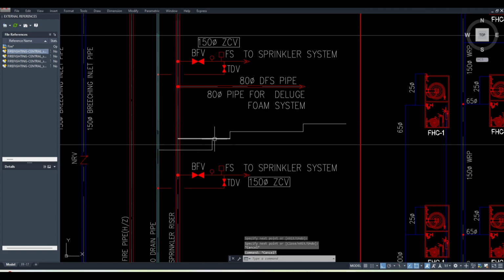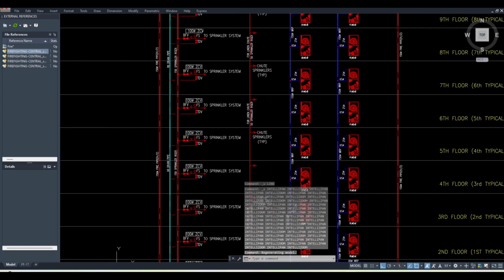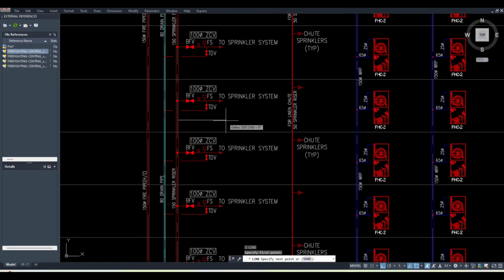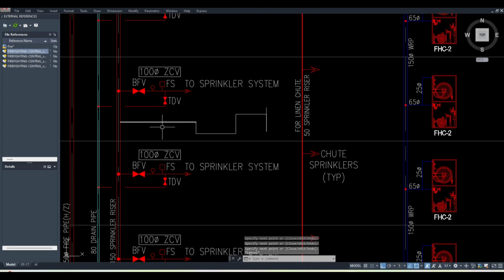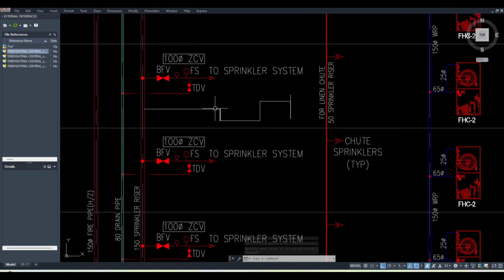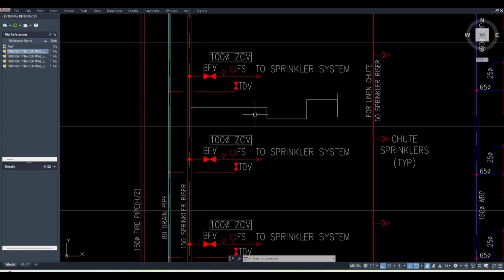But if you do this piping in such a way that, suppose I'm making the piping from here to here, and then I'm going down, and then I'm going up, and then I'm going down, and if you try to do like this, then what will happen? The water cannot come here and drain. The water here will not go up by itself, by gravity. So you cannot drain this. It will trap here. So in that case, here also you have to give the drain point. So what is the purpose? To avoid giving drain points everywhere, because we have to connect the flexible hose, and then we have to take it to the nearest floor drain. So better is to do the piping in such a way that your drain can happen smoothly.